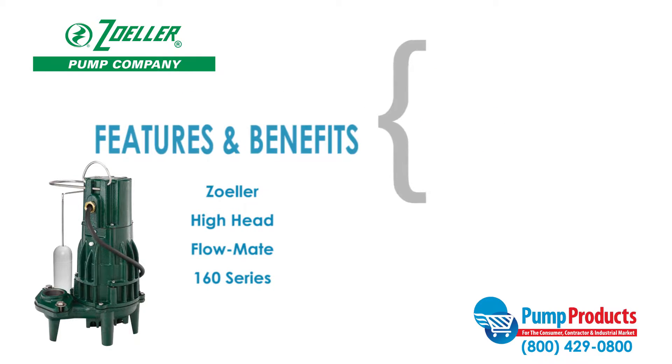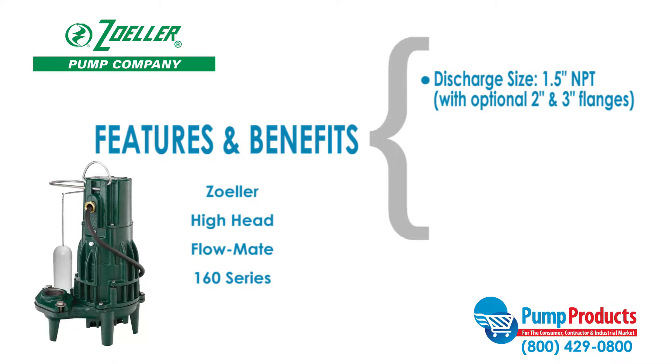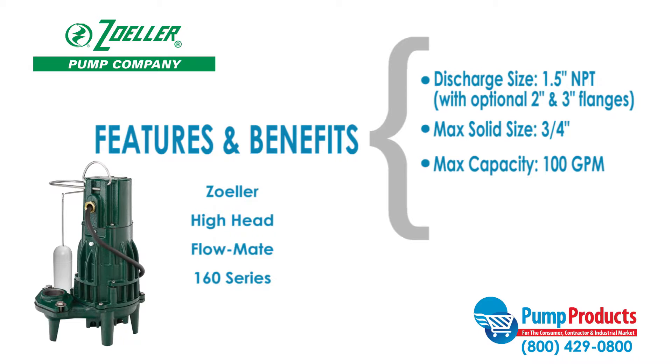Some features and benefits of the Zoeller 160 Series include a discharge size of 1.5 inches NPT with an optional 2 or 3 inch flange, a max solid handling ability of 3/4 of an inch, maximum capacities of 100 gallons per minute, and a maximum head of 86.5 feet.